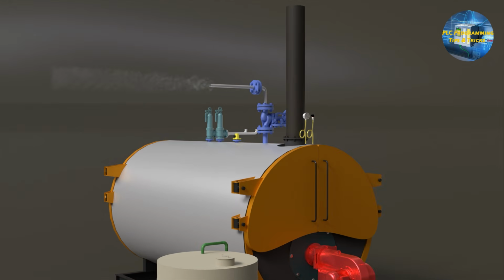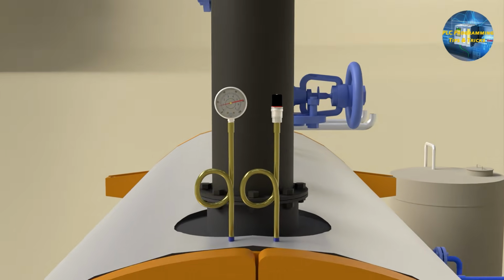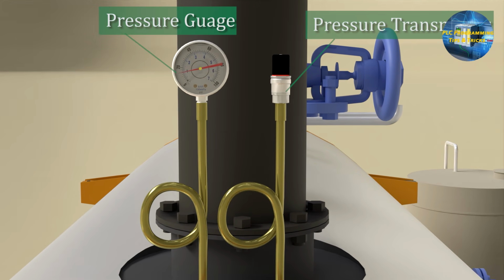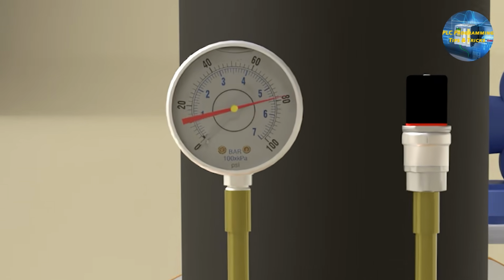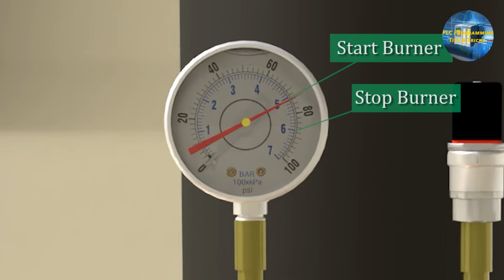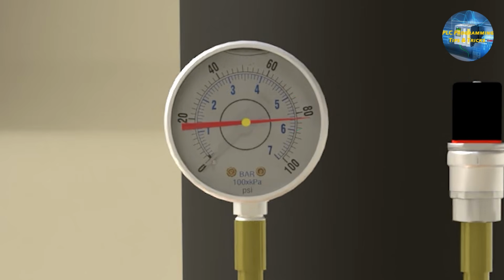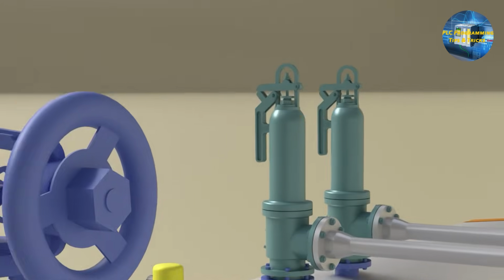Now let us discuss the control system of the boiler. Usually a pressure transmitter is installed on the boiler to monitor the steam pressure. A pressure gauge is also installed as a quick reference for the boiler operator. Now the boiler has a working pressure set point. Once this set point limit is reached, the boiler control system will shut down the burner. When the pressure drops below the lower limit, the boiler control system will again start the burner to make fire and heat source inside the boiler furnace.